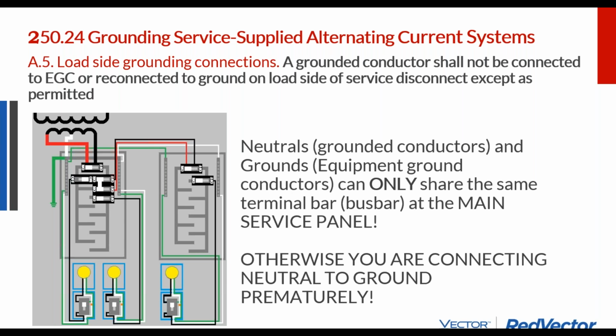Your ground is 0 volts, and your neutral should be 0 volts. And to make that neutral 0 volts, we connect it directly to ground. But the difference between having multiple neutral to ground connections and only one where it's supposed to be is the difference between a water balloon with the water coming out the neck of the balloon, or a water balloon that's full of holes and water is just spilling out everywhere and maybe the balloon will pop.